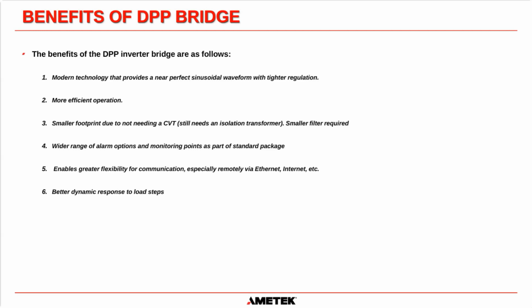It's also got a smaller footprint due to not needing a CVT, which is a rather large transformer. Also a smaller filter is required because the PWM is so similar to a sine wave. We don't need as many capacitors as the ferroresonant system needs. Also a wide range of alarm options and monitoring points as part of a standard package. Because it's much more electronic and much more up-to-date, the DPP system, we can do so much more monitoring of that system.